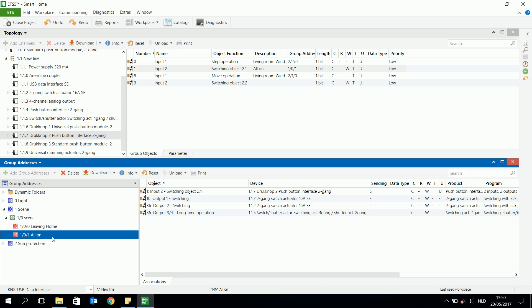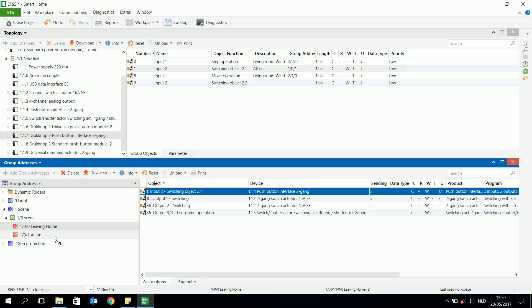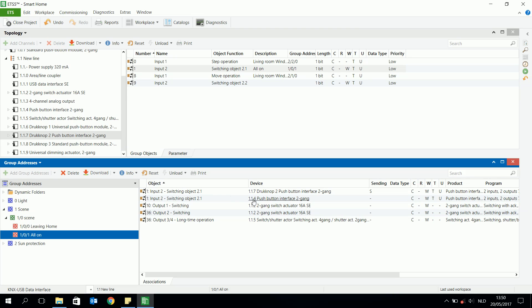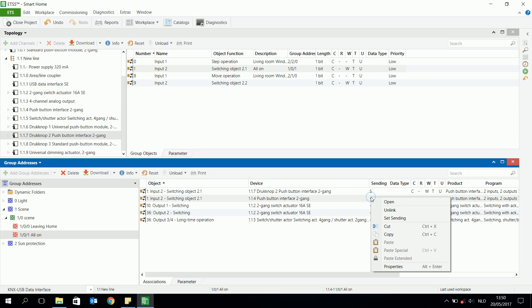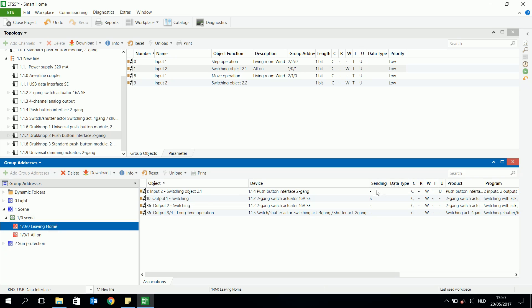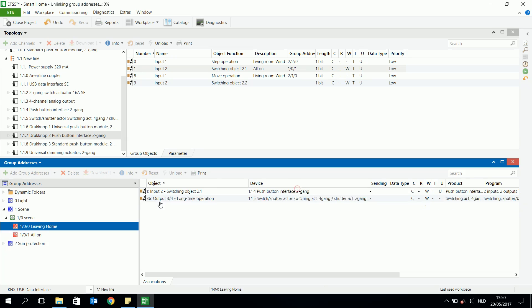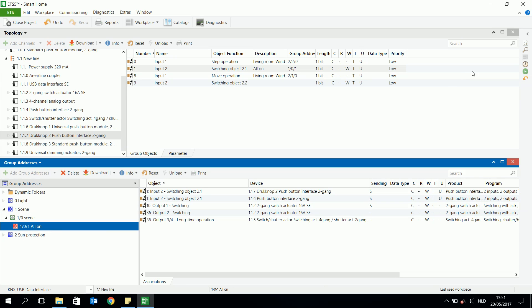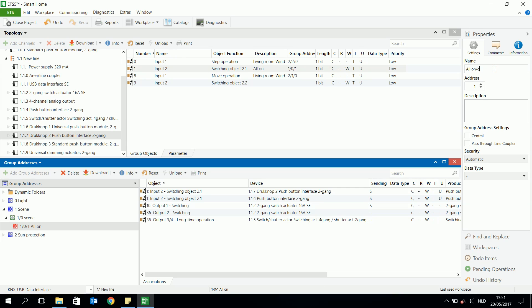What I want to explain is that I use one group address instead of two, to send both an on and an off signal. I'll use input 2 of device 1, which sends an off signal, and this sends an on signal, but I can combine them in the same group address. I need to set one as sending and the other won't be sending anymore. I can rename this group address to 'all on/off', so these two input objects will send an on and off to those output objects of the actuators.